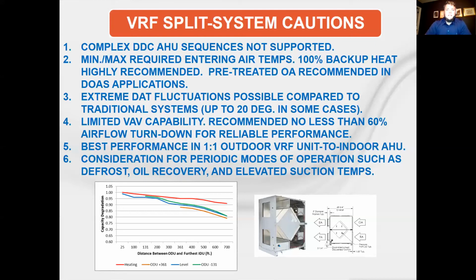And other than that, the final note when looking at VRF applications is to consider the different modes of operation that we're not used to with traditional DX split systems or chilled water. There are periodic smart modes built in, such as defrost mode, where inherently it's a heat pump. So in our cold Chicago winters, it's going to have to defrost that outdoor coil every so often. There's going to be some sort of hit in performance as it goes, even if it's multiple VRF systems staging to overcome when one is on defrost. Still, there's going to be a hit on performance. It's not going to be constant. So just be prepared, and hopefully the application allows for these variations.